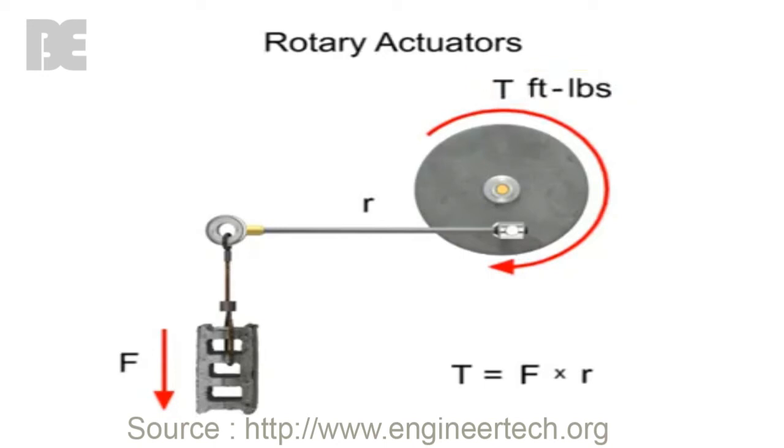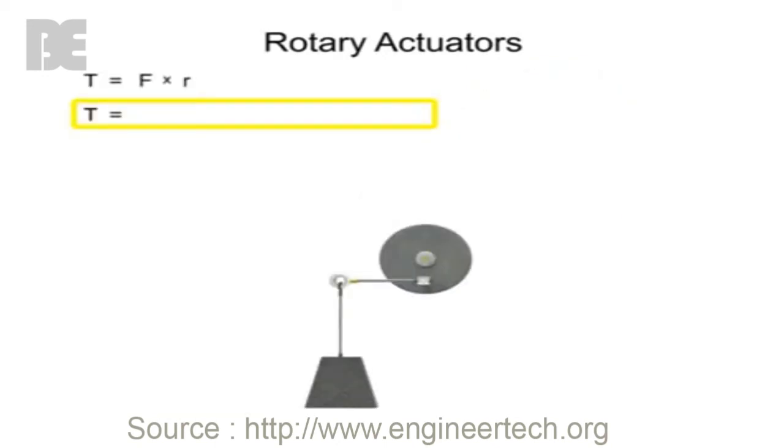For example, if a rotary actuator with an arm length or radius of two feet were used to lift a 200 pound weight, then the resultant torque required to accomplish the work would be 400 foot pounds.